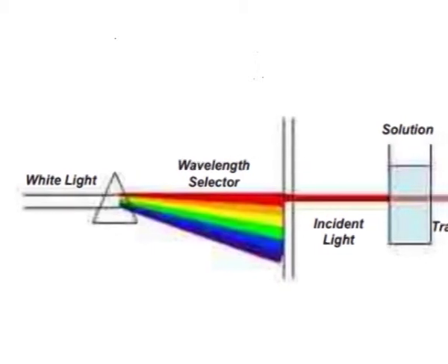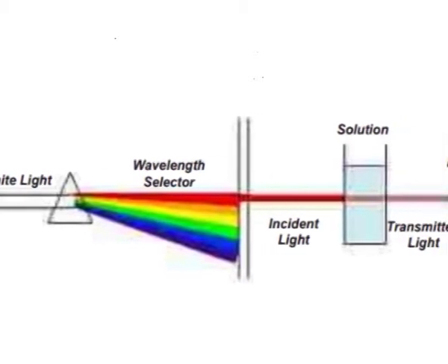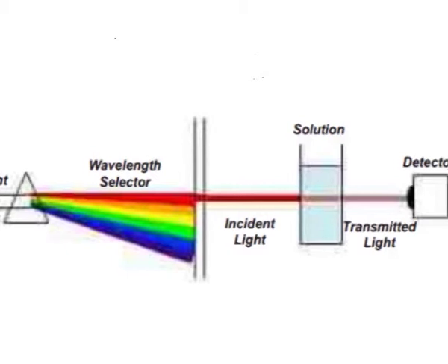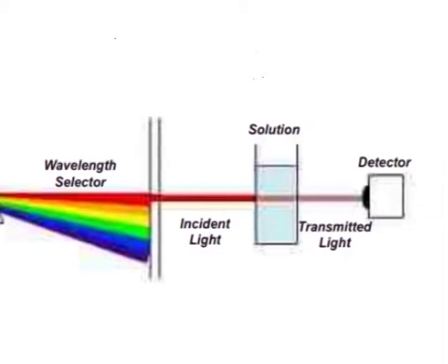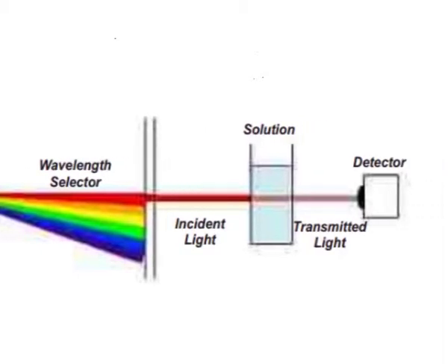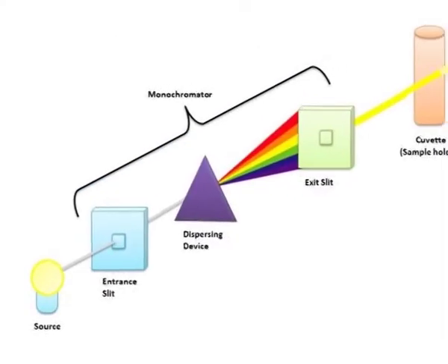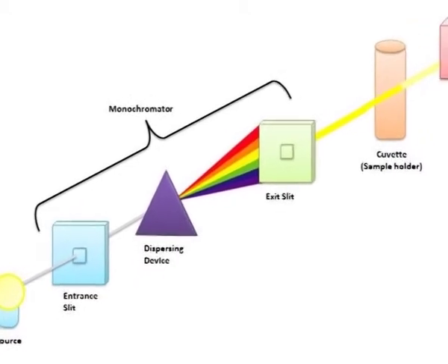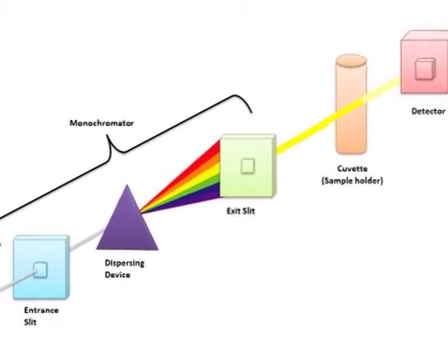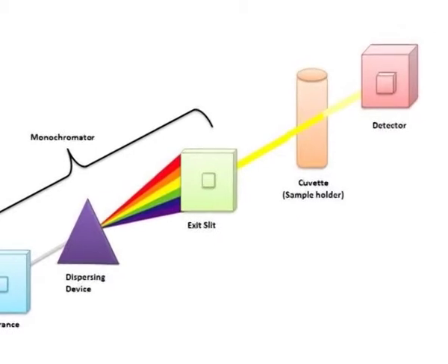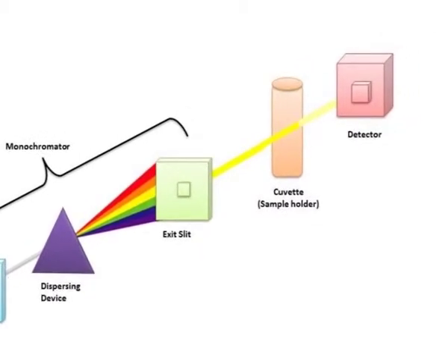If a parallel beam of radiation falls on a prism, the radiation of two different wavelengths will be bent through different angles. A prism may be made of glass or quartz. The glass prisms are suitable for radiation essentially in the visible range, whereas the quartz prism can cover the ultraviolet spectrum also. It is found that the dispersion given by glass is about 3 times that of quartz.